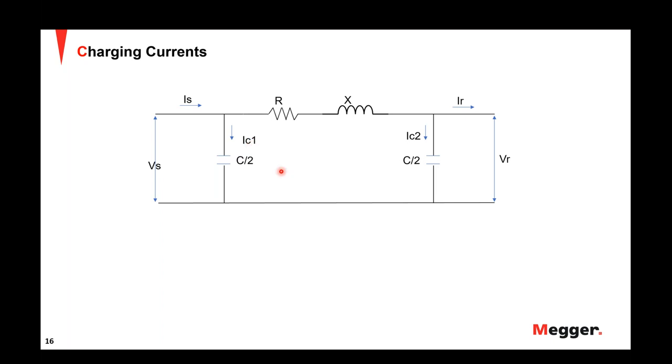The third method is voltage-based compensation. So the change in voltage over time is taken into consideration, and the relay dynamically compensates for the charging current. The way it does this is that it measures the actual charging current, and then it removes that from the differential in real time. So there are dynamic compensations as well. Depending on the application and system, the appropriate one could be chosen.